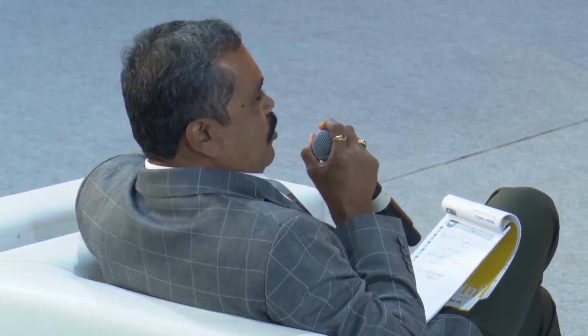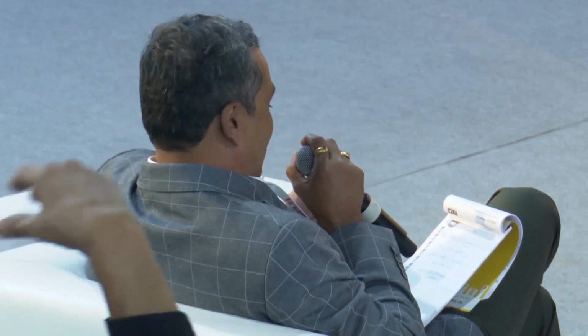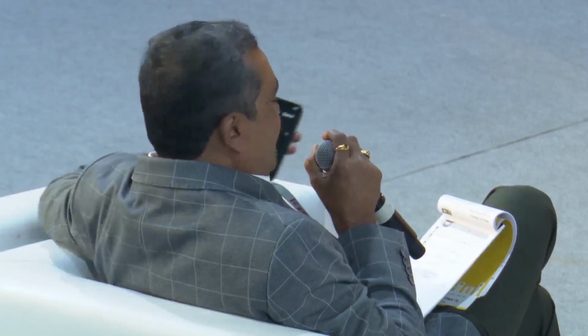In this regard, I would like to bring your attention to guide us. Sir, the standard is IS 3043. From 1966 until 2018, the standard never talks about connecting your transformer neutral separately to an earth pit. The standard never talks about connecting the body of your DG or the body of your transformer to a separate earth pit. This was never written because it is against science. But everyone is doing the same thing. Yeah, it was a practice.